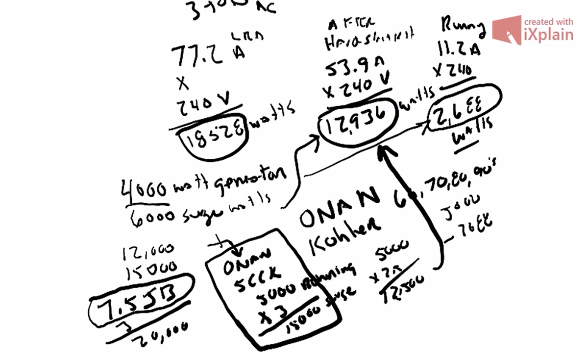And so if you look at what I spec'd out here and the hard start kit, even without a hard start kit, I would have most likely been able to start that with this 7.5 JB. But now that I got that kit in, I reduced that a lot to 12,936. So I feel very comfortable that a 7.5 will work in this environment.